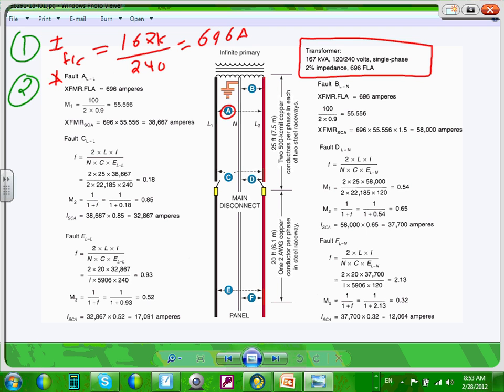There's a multiplier called M1. You take 100. Can you see the impedance here? Everybody can see 2 is the impedance, the 2% impedance. They multiply it by 0.9 always because they assume that it's plus or minus 10%. If something is plus or minus 10%, always minus 10% is the worst. The low impedance is the worst because it gives you more current. Okay? So this is how they came up with a multiplier of 55.56. And then you multiply this multiplier by the full load current and get the available short circuit right at this terminal.